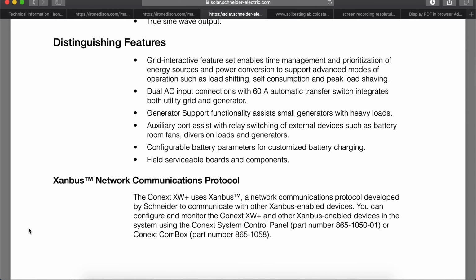Distinguishing features. Grid interactive feature set enables time management and prioritization of energy sources and power conversion to support advanced modes of operation, such as load shifting, self-consumption, and peak load shaving. Dual AC input connections with 60 amp automatic transfer switch. This is built in, integrates both utility grid and generator. The generator support functionality assists small generators with heavy loads. Auxiliary port assists with relay switching of external devices such as battery room fans, diversion loads, and generators.